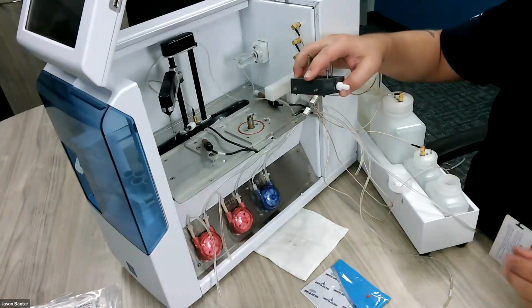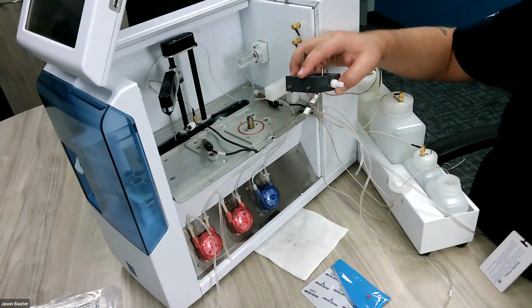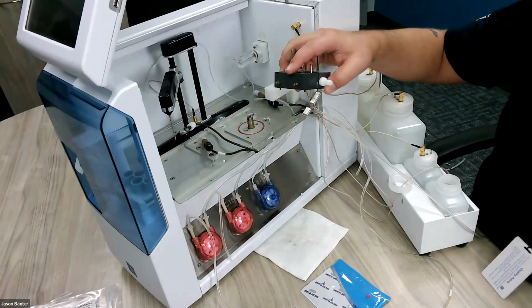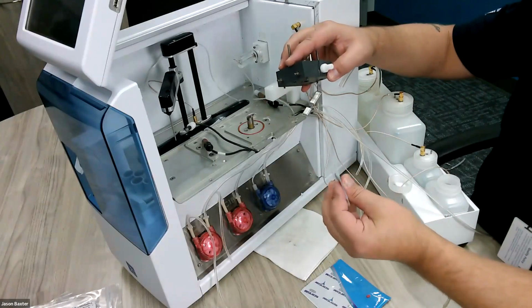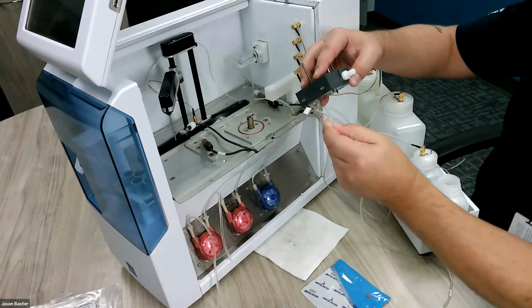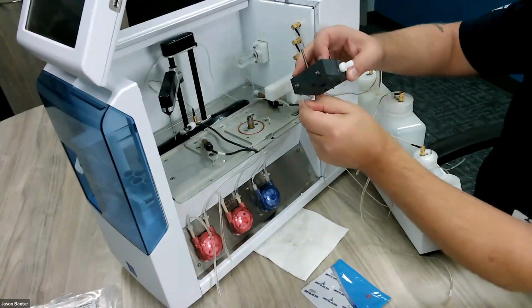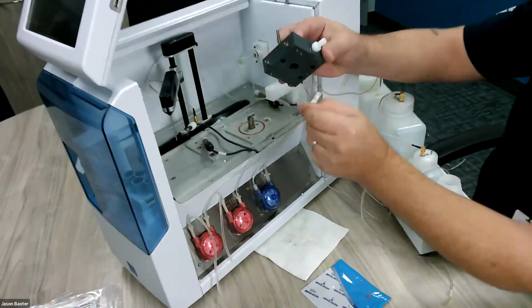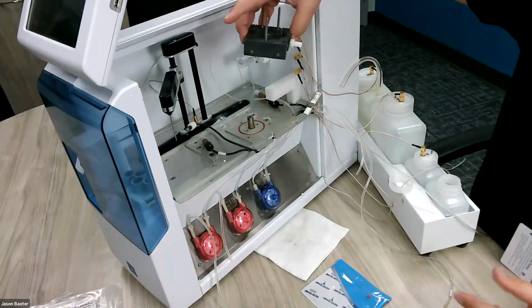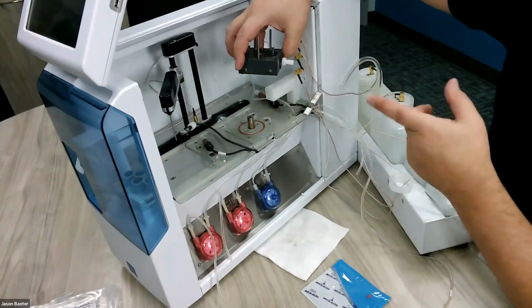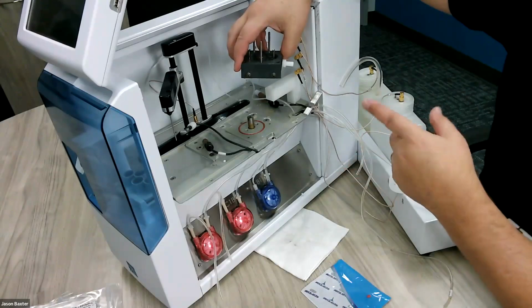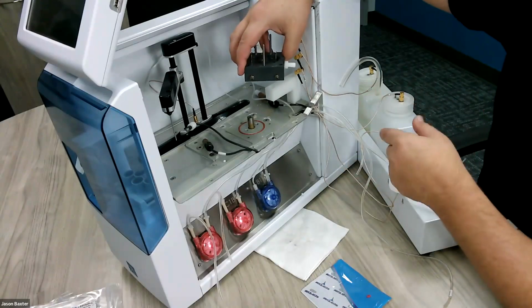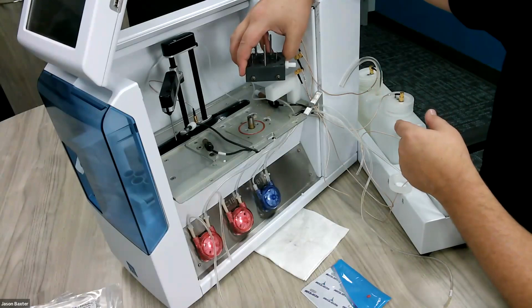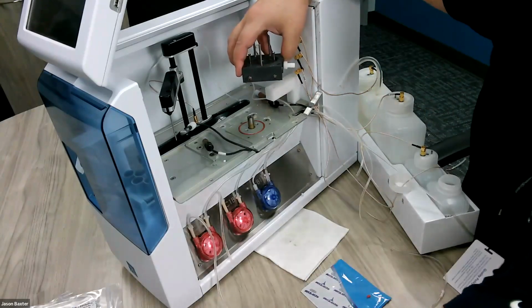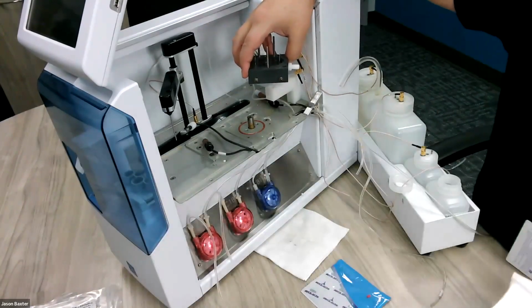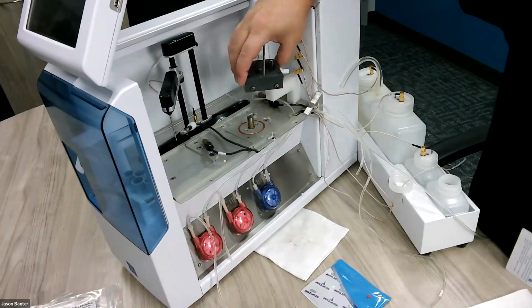This is where I was advising you folks to keep some of this grease handy. One thing that'll really save yourself a lot of trouble in future PMs is to take a small amount of this grease and apply it to the heads of these 3 bolts that are sticking down in here. The reason being is these bolts are stainless steel, the deck is aluminum, and if you have a fluid leak, those 2 components can corrode together very easily, and it makes future removal very, very difficult. If you apply a small amount of grease, you'll prevent corrosion and you'll make your future PMs go way, way easier.